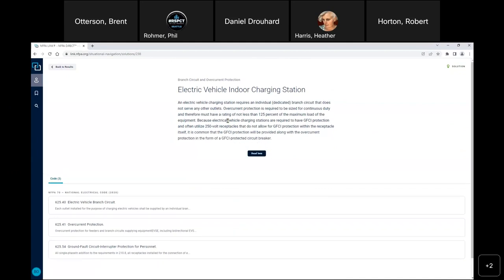This slide explains that overcurrent protection required for continuous duty must be sized at not less than 125% of the maximum load of the equipment, which is easy to find because it'll be on the nameplate rating. It will also say it requires GFCI protection.